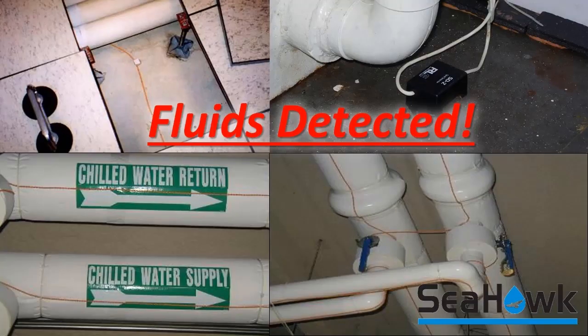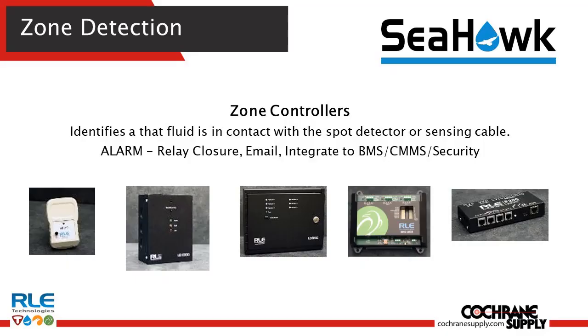The purpose of the leak detection is to detect fluids. Could be under chilled water supply and return lines, could be under raised floors, could be any other critical application where you're trying to protect your assets. Monitor, integrate, alert, provide peace of mind. That's why we exist. So the purpose of a zone controller is really to identify a fluid leak in a space that it shouldn't be, in a particular zone.